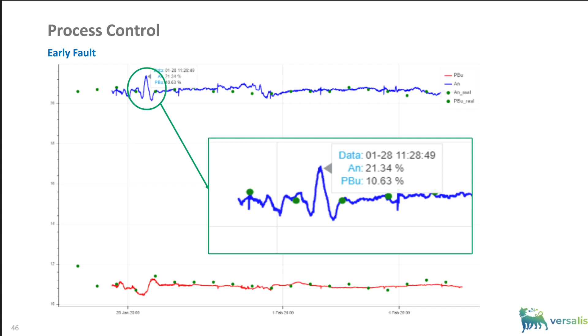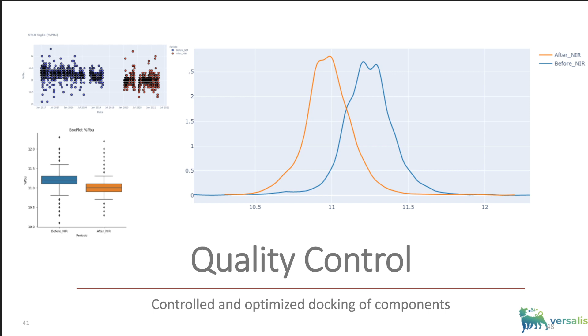The orange curve is almost a perfect Gaussian, significantly narrower and centered on the product target value. In this case, it is shown how the addition of a component to ensure product quality, with real-time control by NIR, can be managed much closer to the threshold value, the lower value in this case, providing important savings. The variable monitored here concerns the amount of rubber added to an anti-shock polymer. In fact, while still maintaining the final product quality, there is a saving of around half a percentage point in added material, which on a large-scale production plant brings a significant economic advantage.